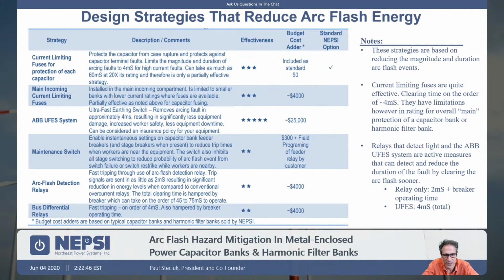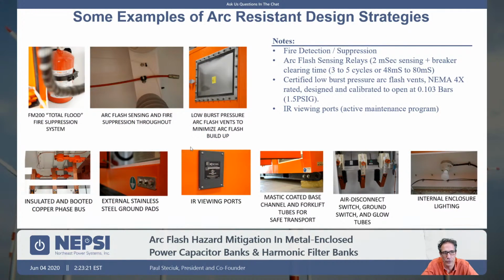We have a very fast detection of the event, but then we have to wait for the breaker to clear the condition, and that's anywhere between 3 to 5 cycles. Bus differential relays is another great way to speed up the fast tripping within a metal enclosed cap bank. We're going to be talking about this ABB UFES system in just a moment, and this is a very interesting device. It is designed to not only make it safer to operate for operational personnel, but it also provides an insurance policy for the equipment.